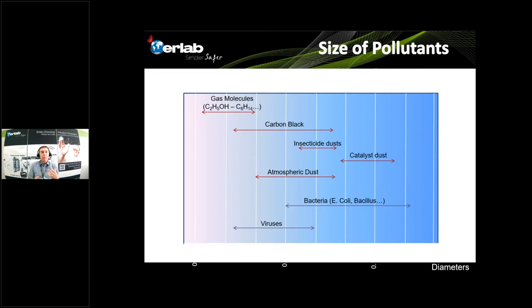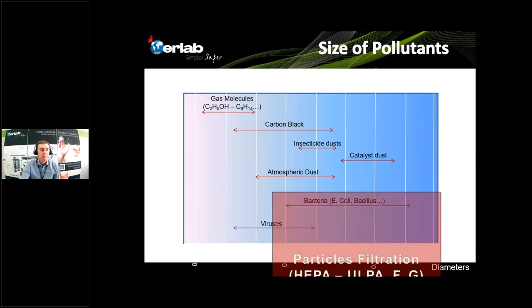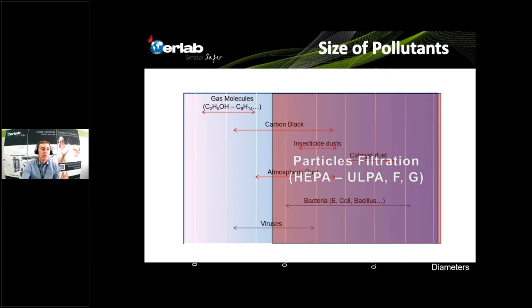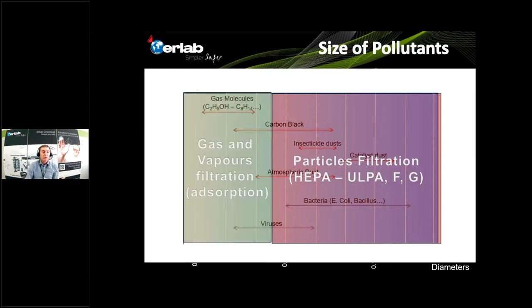When we talk about this pollution in laboratories, there are two major technologies used to trap them. For the largest particles — liquids or solids — we use particulate filtration, performed with HEPA or ULPA filters. For gases or vapors, we use molecular filtration, also called adsorption, which is most of the time performed with activated carbon.